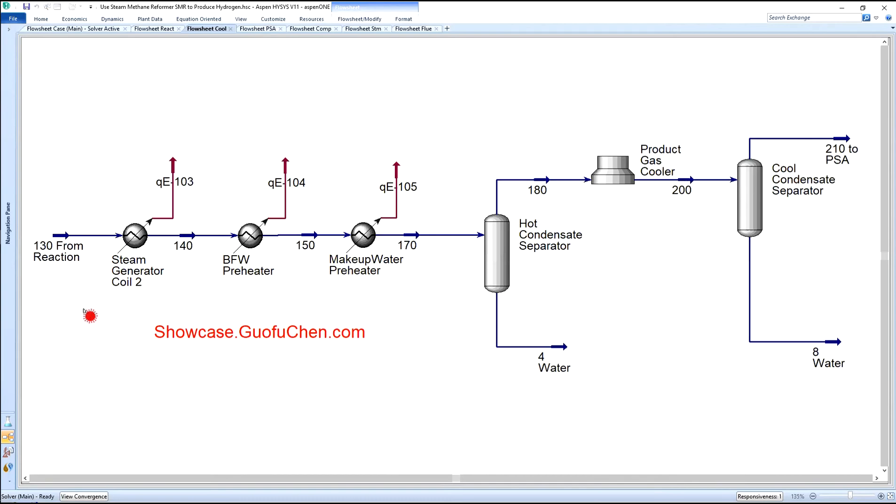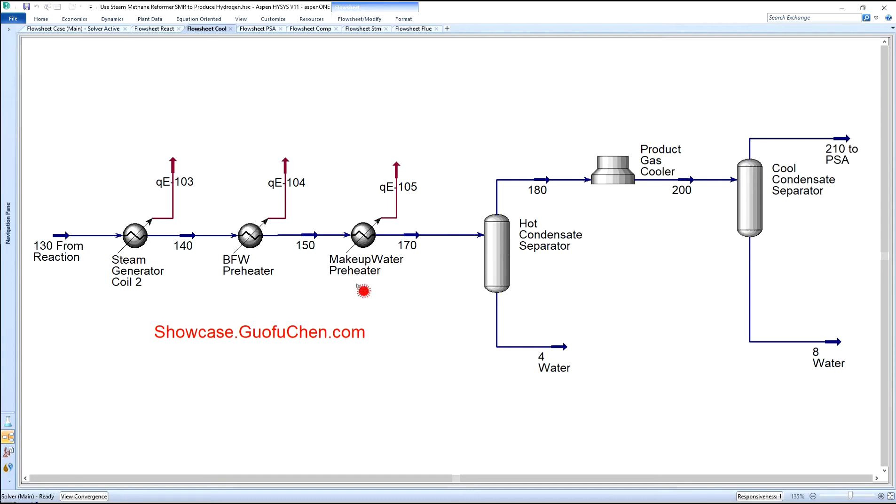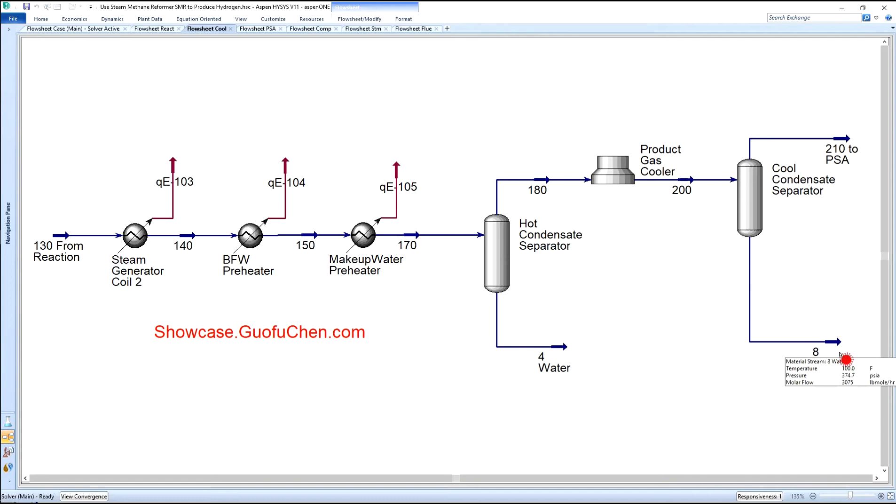The cooling module is primarily used to remove water. At the same time, the heat is used to generate steam. The mixture gas is further cooled in steam generator coil number two, then boiler feed water pre-heater, then makeup water pre-heater. Liquid water is separated out in a separator, then the gas is cooled to ambient temperature to further remove liquid water.